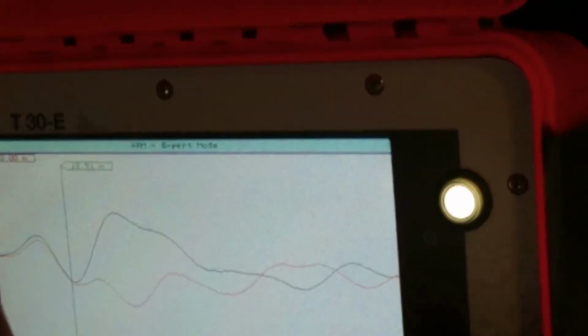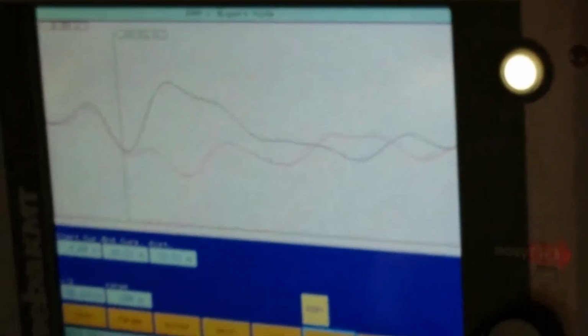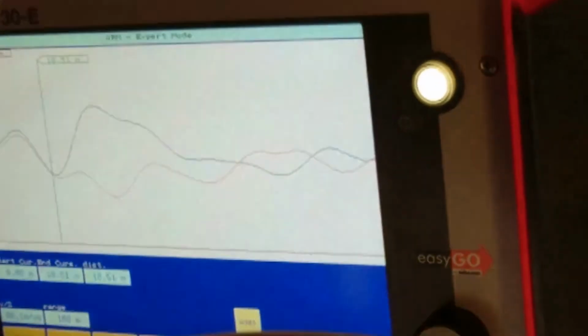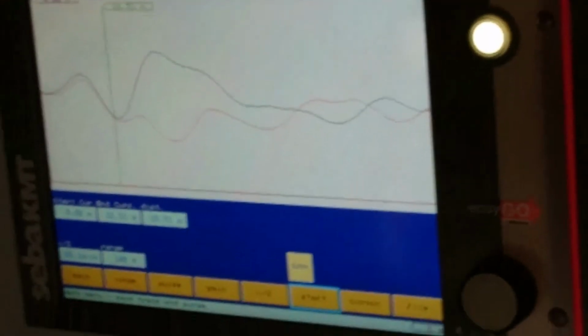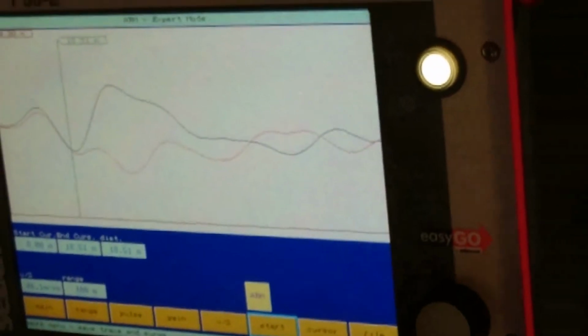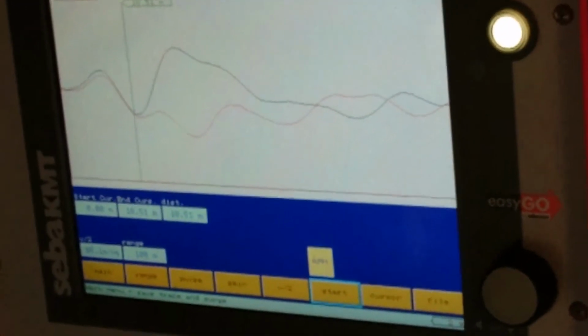Again, sometimes this cursor will not go automatically to the faulty area because of how critical the fault is, or if you have a longer cable with joints, there are a lot of extra reflections here that aren't very clear.